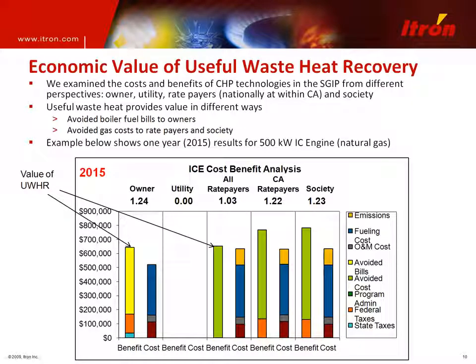And we see that useful waste heat really provides value in different ways. Right away to the owners, it's avoided boiler fuel cost. If you look at this chart, this is really one snapshot from a fairly comprehensive model. We're looking at a 500 kilowatt natural gas fueled IC engine, in the 2015 year within the model. We actually looked at these over the measure life, the entire CHP life, and on a levelized cost basis. So looking at 2015, you can see with the yellow bar the benefit to the owner: quite a substantial difference between cost and benefit, on the order of 30% benefit to the owner for that particular year.